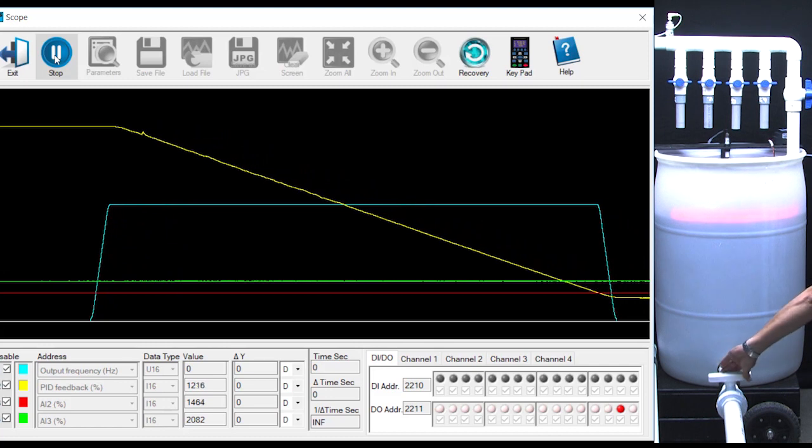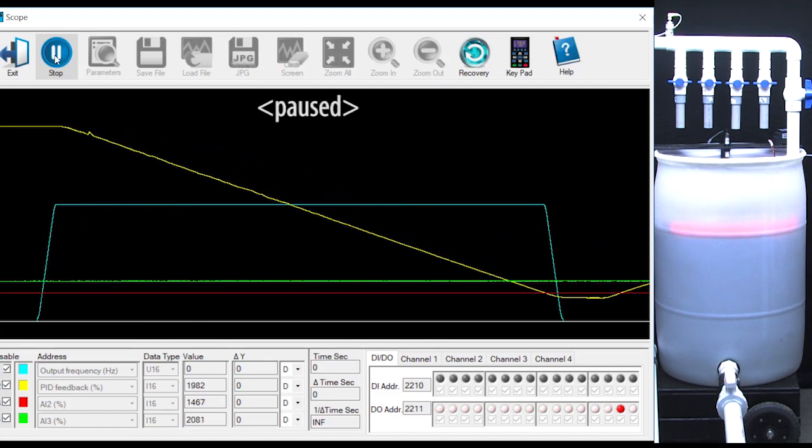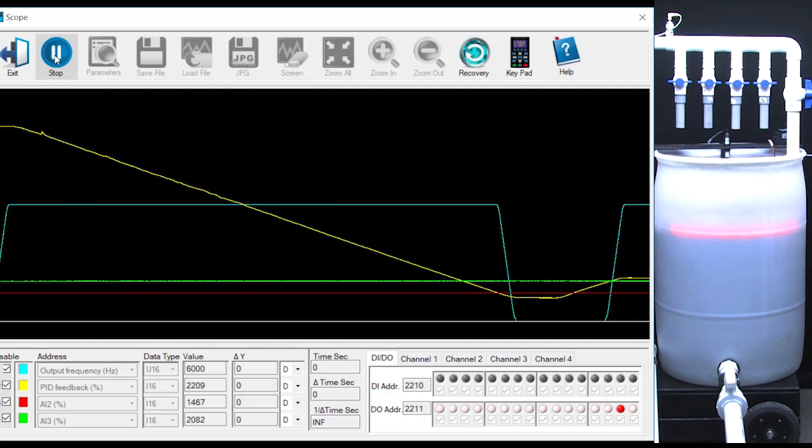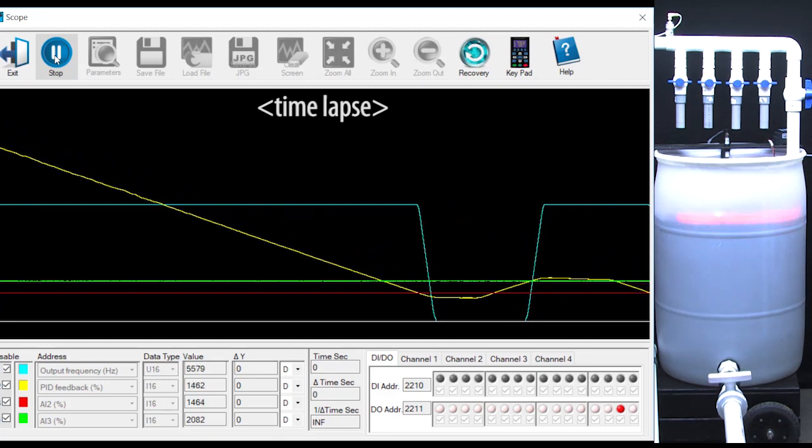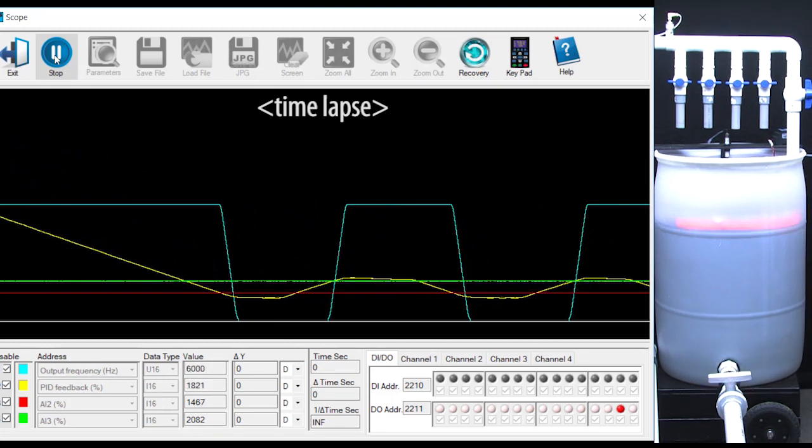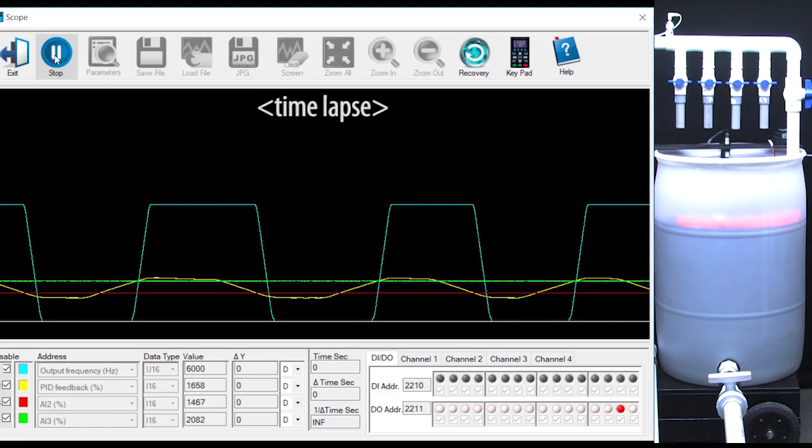I'll open the valve to simulate demand. The yellow process variable starts to increase telling us the tank level is decreasing. When it crosses the green wake up level, the motor starts back up and fills the tank again. Let's speed this up and watch a few cycles. The GS4 drive is now automatically controlling the cycling of the pump in a reverse acting system.